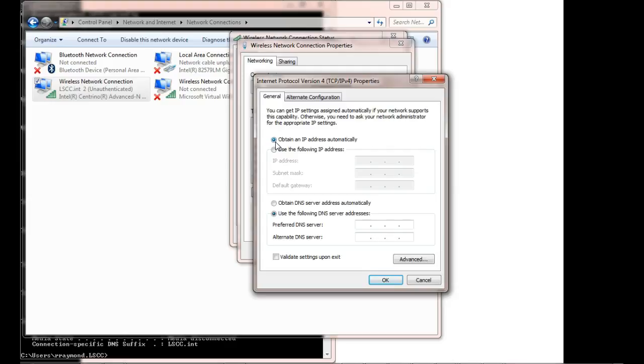So these guys over here, we don't want their IPs to change, right? We don't want them to move around. Because if we go over there and turn off that line, you understand, and then we leave it off for a certain amount of time, depending on how long the DHCP server is set up to reserve those IPs, then I got a different IP. Now my HMI panel doesn't work anymore because it doesn't know where the PLCs are, because we're using dynamic IPs. Does that make sense?